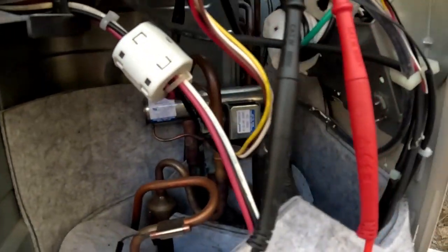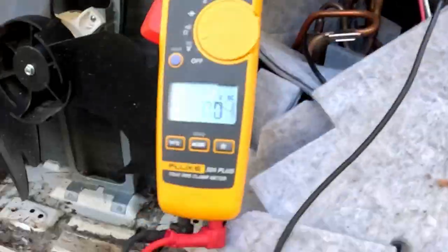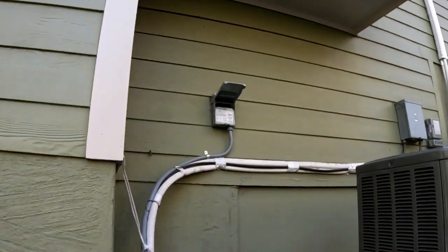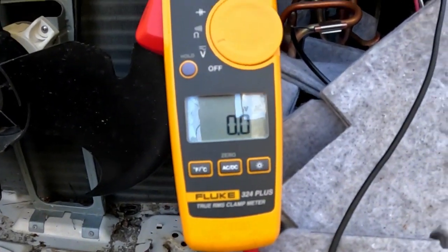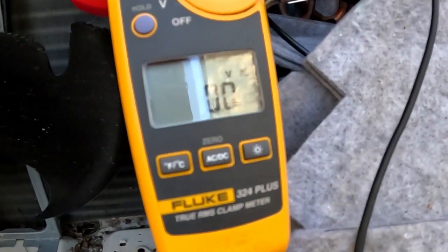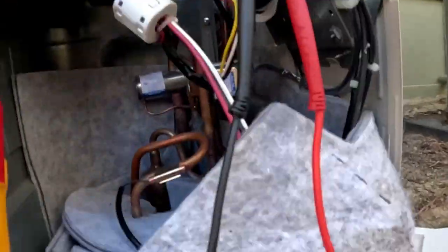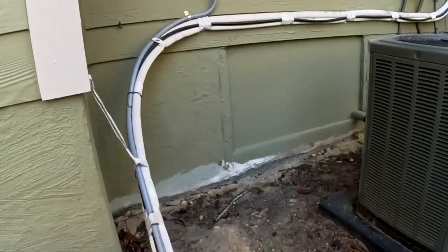Evidently Ring's got their fingerprints on this. I don't know. But that thing is a, if you look at it, I don't know if it's blurry or not, but 230 volt solenoid for that reversing valve. So I'm going to plug into that. Then we're going to reset the disconnect, and we're going to watch this thing, and when it resets inside and calls for heating, we're going to see if we get a pulse of 230 or if it maintains 230 or we don't get anything, just to confirm that we have a problem with this board.